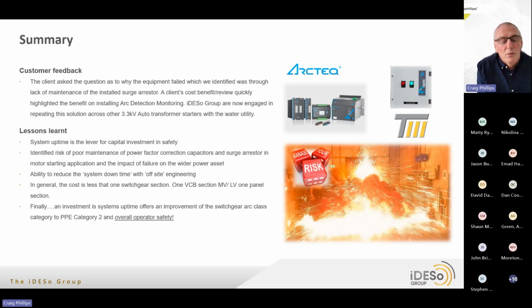One thing worth noting is that there has been a lot of discussion in the chat about the cost of arc quenching, the cost of relays, but in general, it's very much less than one section of a medium voltage vacuum circuit breaker or one LV panel section. And how often have I been to site and looked at a switchboard and there's power factor correction sections there, and the client says, I'm not using those, but he's purchased them during the initial design and during the initial project.